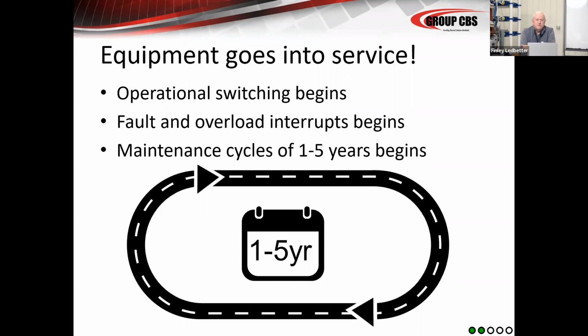If it's in a dirty environment, it's being used, it's a very critical breaker, a very critical circuit. It's in an environment near the ocean. It's in an environment near a chloride or something that produces chlorides. It's in a dirty environment. You probably want to increase that maintenance cycle. Breakers don't like to be fully loaded, unloaded, fully loaded, unloaded. That creates a lot of thermal issues, a lot of condensate and things. Steady state, low loading breakers survive much better. So all that has to be considered in this. A lot of people use the run to fail method. We're not going to test it until it fails. A lot of people use condition-based maintenance, and we're going to talk about all those techniques in the next sessions.